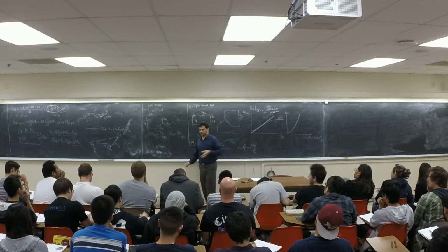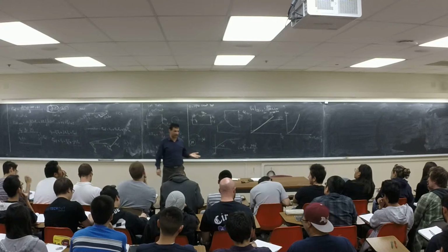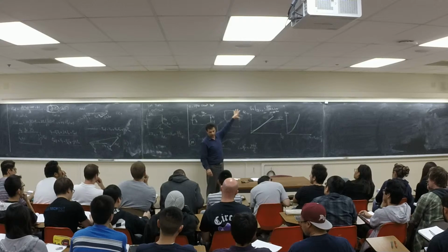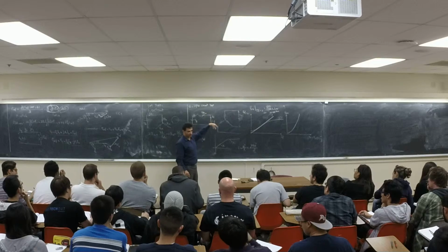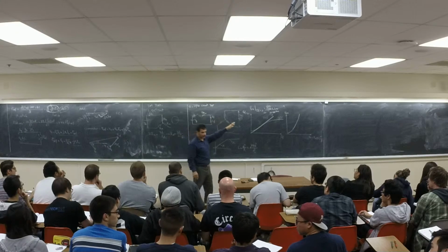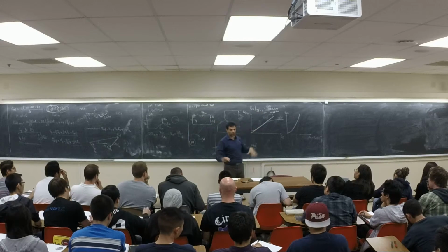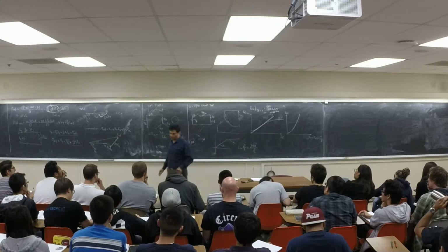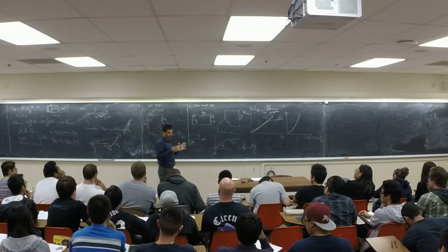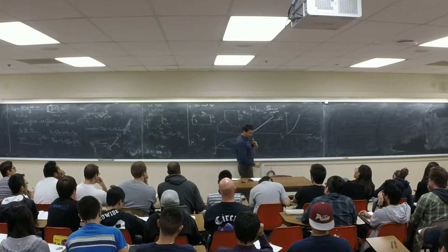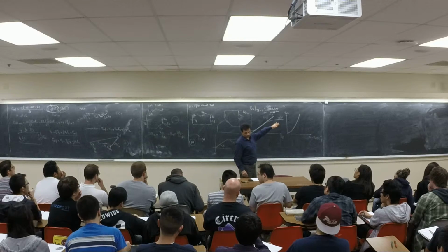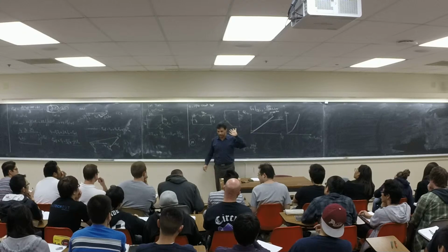For example, they say this synchronous machine is 480 volt, right? 480 volt is the line to line. 480 divided by square root of 3 is 277, right? So basically, you take a machine at synchronous speed, you increase the IF, and finally you see the rated voltage here, which is 277. You stop there. Usually don't go beyond that, or you can go 10% more, but don't go much further because you can kill the machine. The machine has an isolation which is related to the rated voltage of the machine. Now we got to the rated voltage of the machine and synchronous speed.